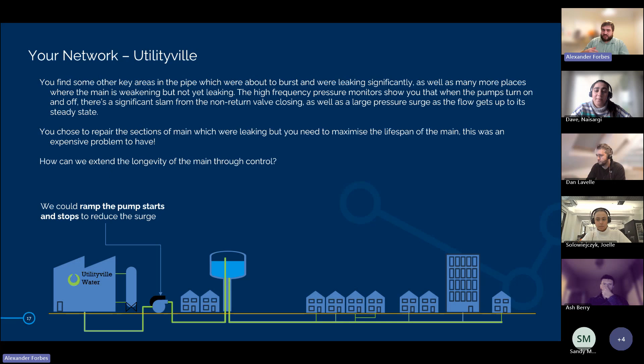So I suppose that would be a pump control, or maybe not, because this is the beacon. I mean, I think this is a condition assessment thing. Or I suppose velocity and water quality. I'm lost. It's fine. So the thoughts that I had around this, since we're looking at just that control, I suppose one thing I've not said in here is we don't have the money to replace the entire main, unfortunately. But we can look at ramping the pump starts and stops to try and reduce that pressure surge, try and get those pressures down at least to hopefully prevent a burst, at least in the short term.